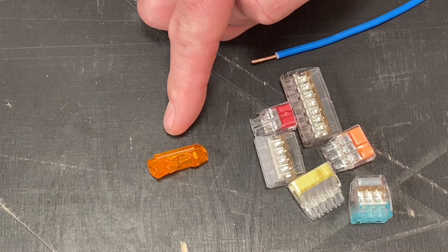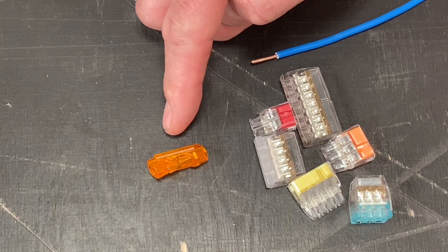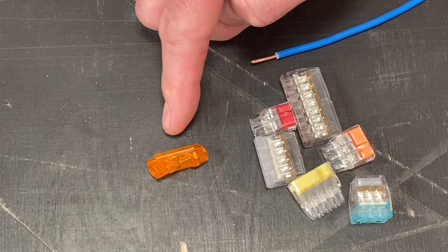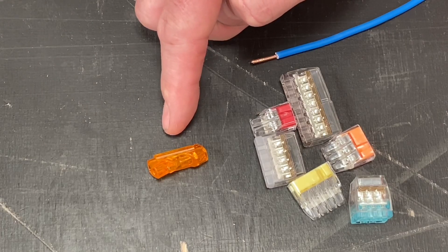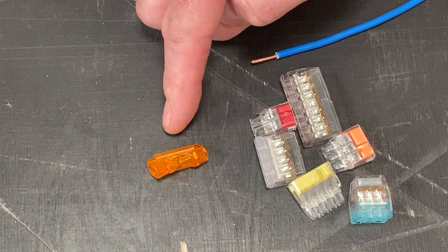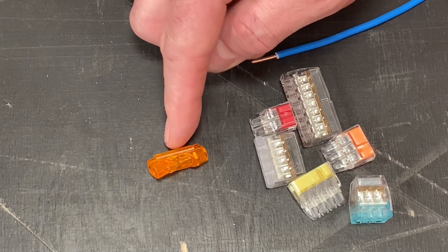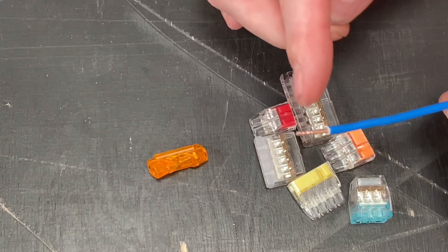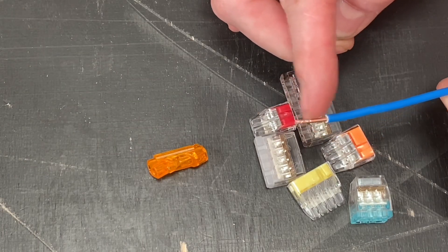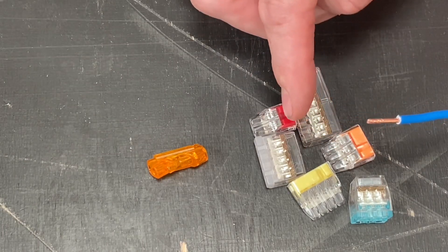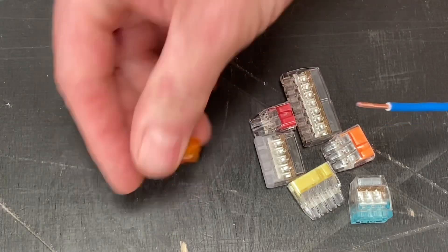Now we have the splice connector. This will do 0.5 millimeter squared to 4 millimeter squared in solid copper, and in stranded copper from 1 millimeter squared to 2.5 millimeter squared. It's also rated at 32 amps. So if we just show it in use, exactly the same as before, 13 millimeters of insulation removed, and then we just push it simply into the splice itself.